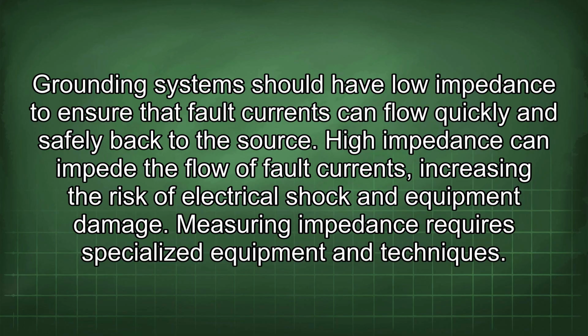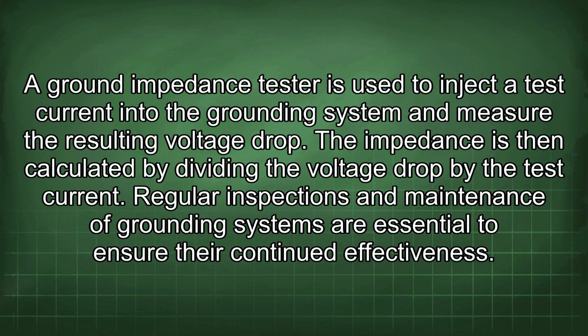Grounding systems should have lower impedance to ensure that fault currents can flow quickly and safely back to the source. High impedance can impede the flow of fault currents, increasing the risk of electrical shock and equipment damage. Measuring impedance requires specialized equipment and techniques. A ground impedance tester is used to inject a test current into the grounding system and measure the resulting voltage drop. The impedance is then calculated by dividing the voltage drop by the test current.